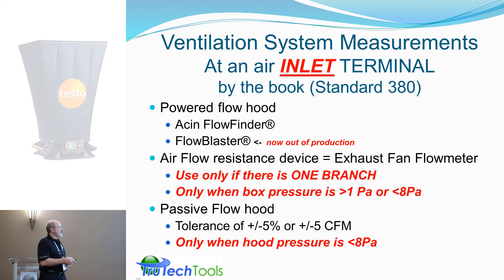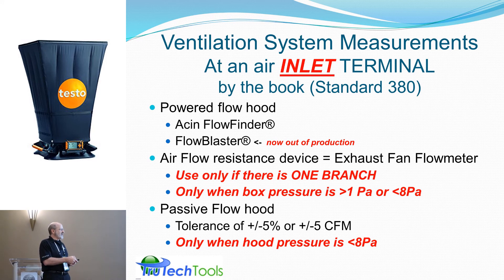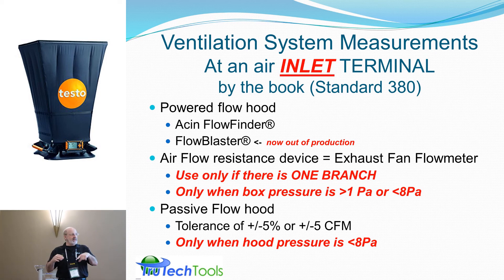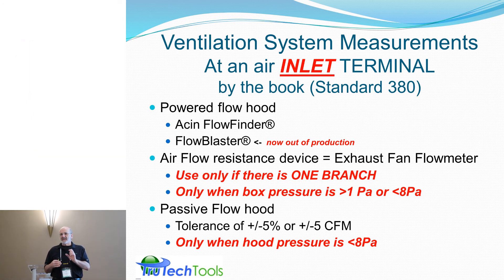Passive flow hoods can also be used for this type of measurement. The tolerance is between plus or minus 5% or plus or minus 5 CFM, but there's another caveat from another standard overlaid in there: only when the hood pressure is less than 8 pascals. So a very small pressure inside that hood — otherwise it's going to start to affect the measurement.